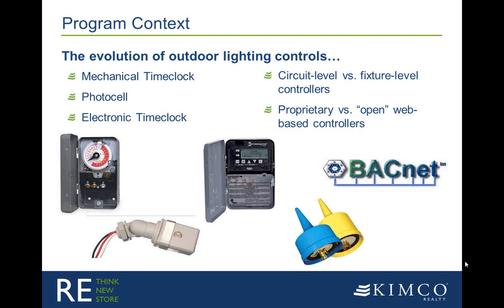Over on the left-hand side, there's a couple categorical classes that I'd like to just mention. Lighting controls can be installed for either circuit-level control or fixture-level control. Most are wired for circuit-level control, meaning that anytime you turn something on and off, you are controlling a group of anywhere from 2 to 10 fixtures or light poles. More than that if you're talking about building lights such as canopy lights or wall packs. But in terms of parking lot poles, potentially probably around 4 to 6 poles per circuit. So circuit level is much more common, and the benefit there is you have much fewer components to install, but you have much less granularity of control.